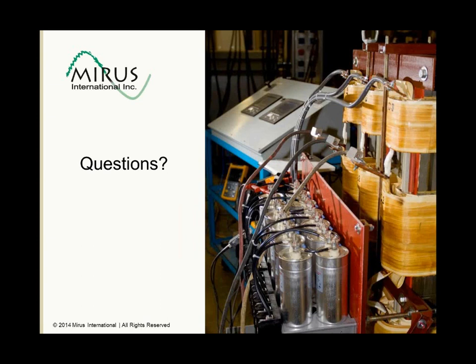But they're also often above the 50th harmonic, and a lot of instrumentation doesn't measure up there. So it might look like the current distortion levels are low or the voltage distortion levels are low. But if you had an instrument that could measure all the way up to the 100th harmonic, you would see a band of harmonics at these higher frequencies.